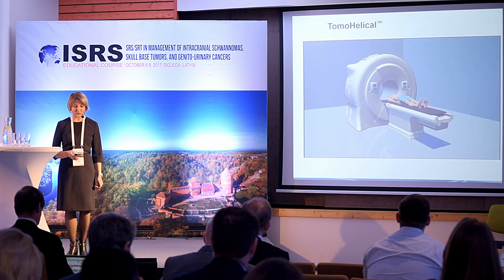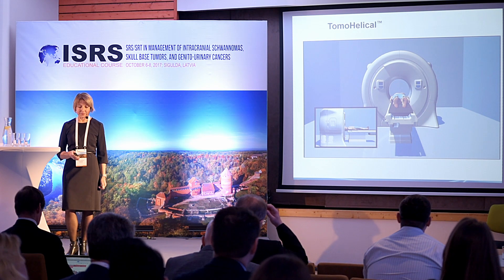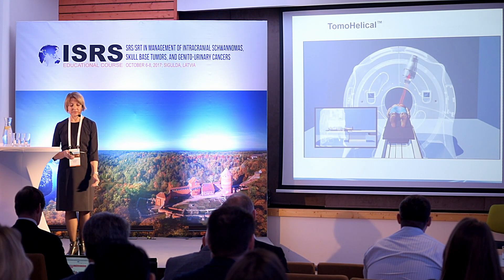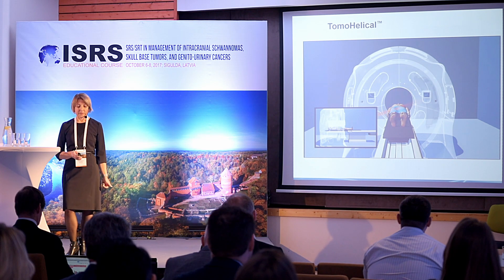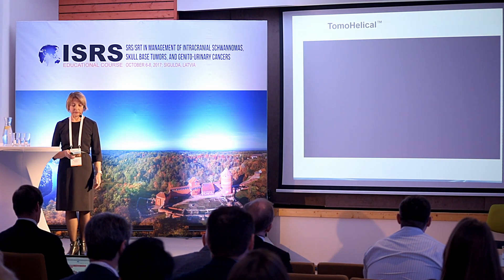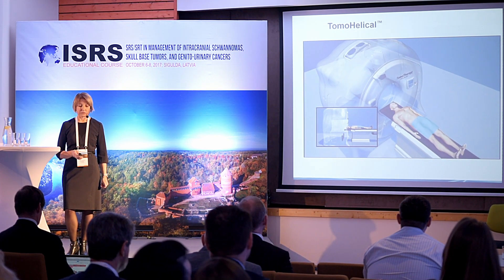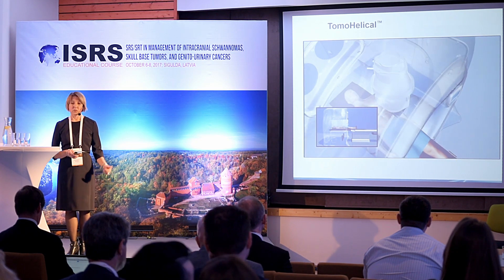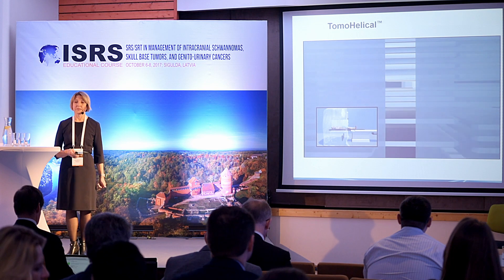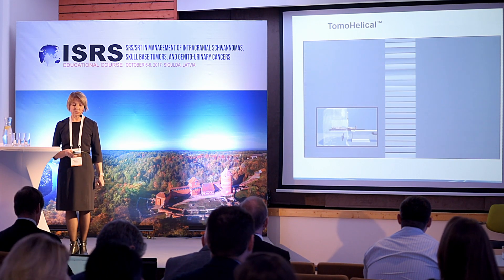Here is a short movie showing how the system works in TomoHelical mode. The patient is set up, the table continuously moves into the bore, and during TomoHelical delivery the system continuously rotates around the patient. Here we introduce the treatment of the prostate, and we can also see how the multi-leaf collimator works inside the system — the leaves open under the target and close under healthy tissue or critical organs.